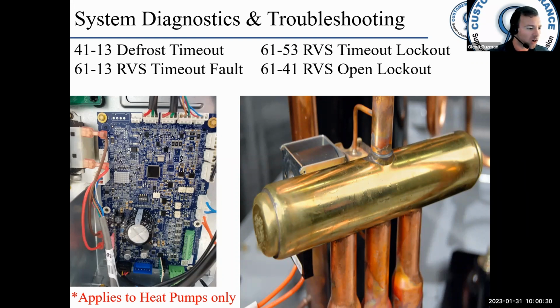The code will be active when defrost is terminated on maximum time and the target coil temperature has not been reached. So typically when a defrost occurs, it's after a certain amount of runtime and the coil meets a certain temperature, you go into defrost, and then it should be terminated on temperature. Once the coil gets above a certain temperature, then it's going to terminate. Defrost is an inefficiency. It is absolutely required for heat pumps, but it's inefficient from an energy conservation standpoint. When you have to terminate defrost based on time and you still didn't meet the temperature, that's when you get the 4113.